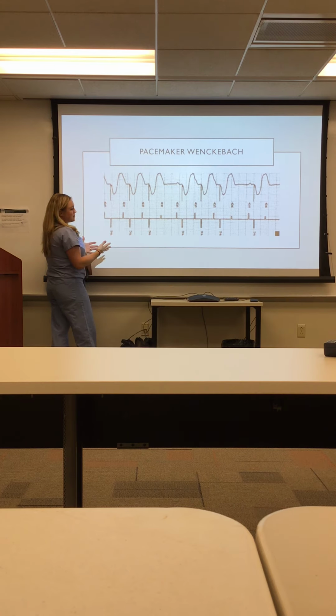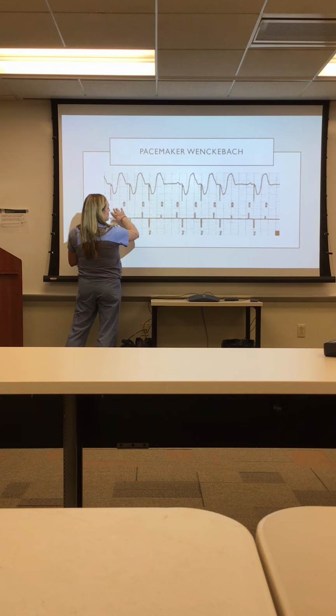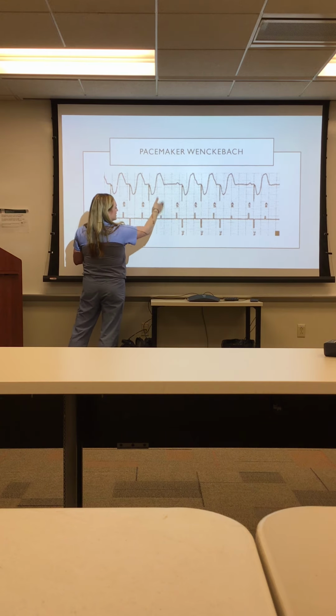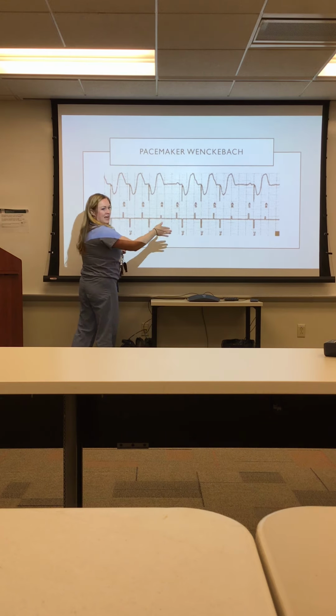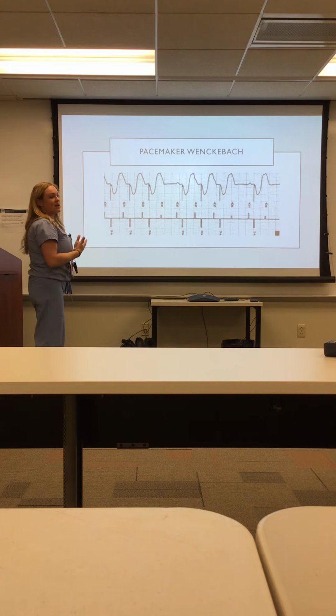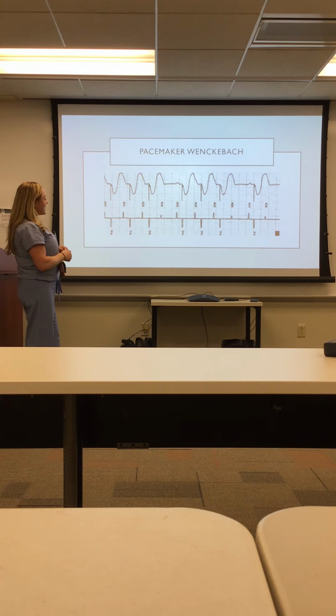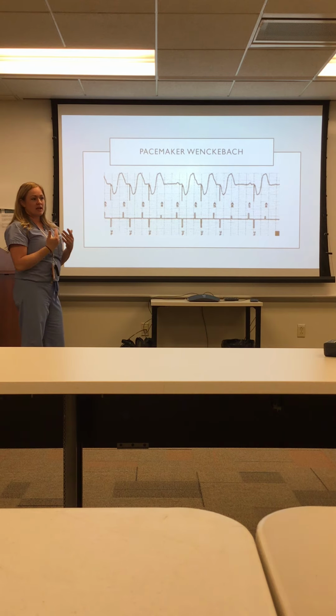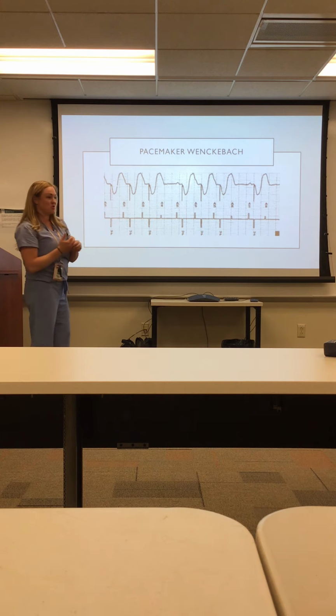So you're gonna see kind of a pattern of 3 paced beats, kind of a delay, another 3, and a delay. So that's a natural pacemaker Wenckebach there. And that's okay, but you would want to either call the EP or the cardiologist, or have one of us come in, because we can program the device at a deeper level to extend that PVARP or extend that timing cycle to either allow it to come in or not. Or rate control will be your friend.